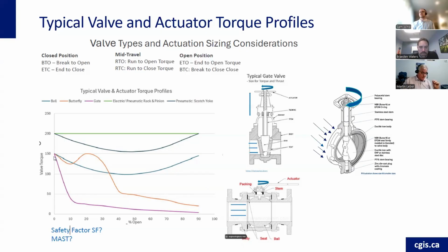There's a steep increase in torque. So in particular, the gate valve will drop off quite quickly, and within maybe 10-20% of opening it starts dropping off already. Now, gate valves may vary depending on the profile of the disc, of the face, but this is just a very simplistic view.